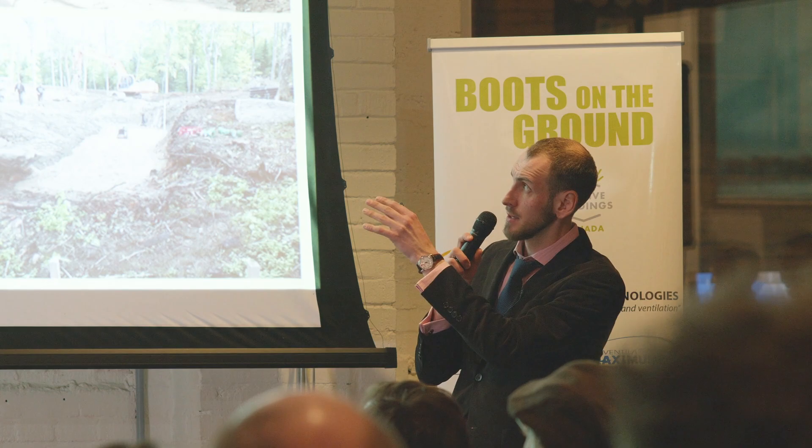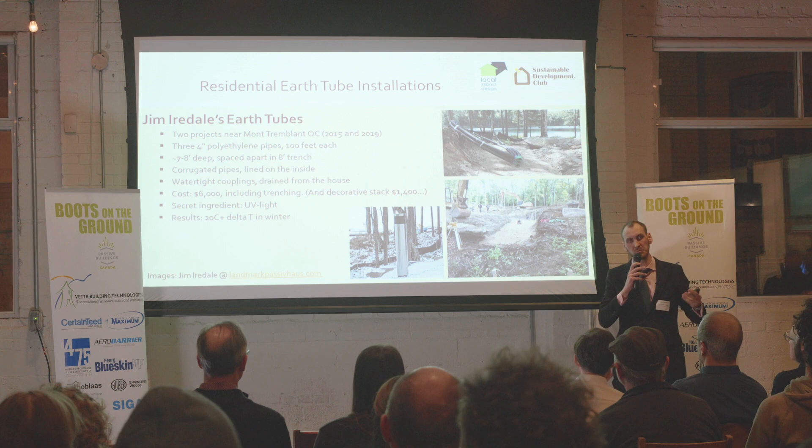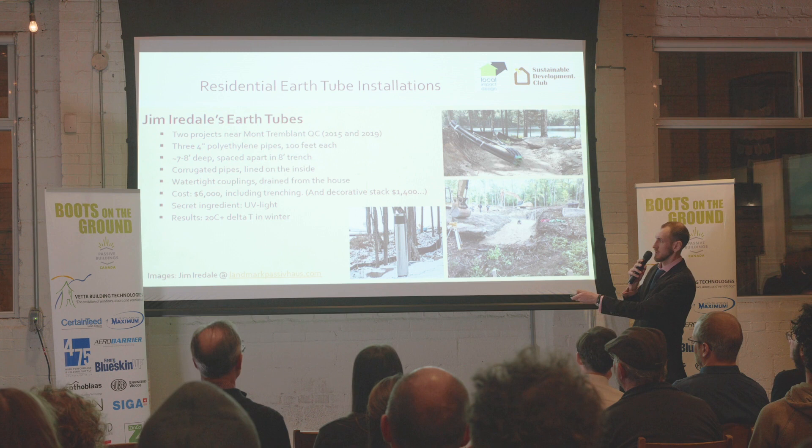This is an example from Jim Iredale's, from Quebec, Mont Tremblant — two projects with four-inch pipes, 100 feet long, buried about seven to eight feet deep, spaced apart. It's corrugated pipe lined on the inside so it's smooth. It cost him $6,000, mostly because of excavation and a nice decorative stack at $1,500. His secret: he installs a UV light in a plenum box at the junction where the pipes come into the house to fight potential mold. He thinks it's overkill, but nice to be safe. The results: plus 20 degrees Celsius.